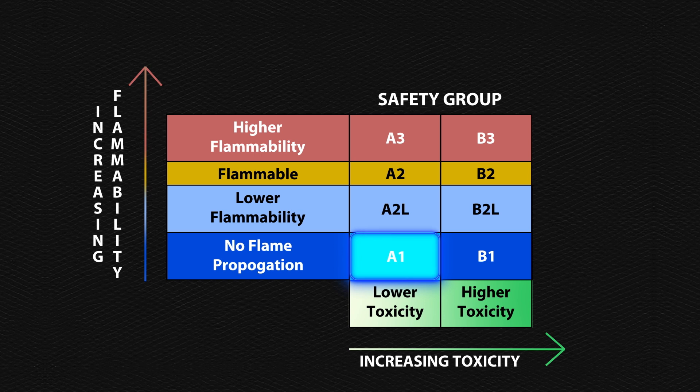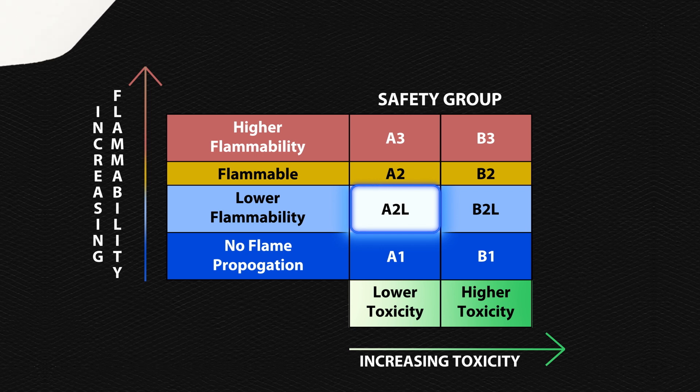ASHRAE classifies refrigerant by toxicity and flammability. A1 refrigerants have lower toxicity with no flame propagation, whereas A2L refrigerants have a lower flammability.